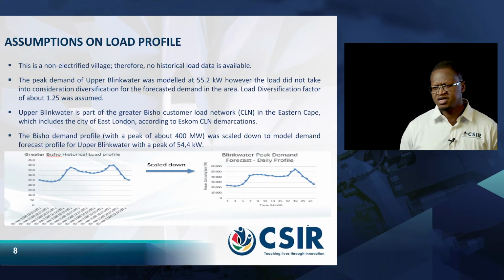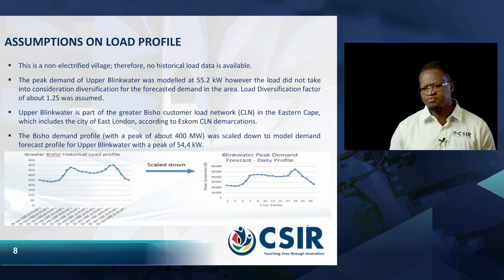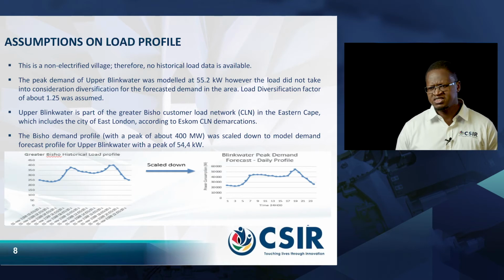In terms of assumptions, the main key assumption was on the load profile. As the village has not been electrified before and is not yet connected to the local municipality in terms of electricity, there was historical data unavailability, so we could not directly get a picture of the load profile. We went to ESKOM and requested the load profile for the larger municipality, the Bisho customer load network, under which the Raymond Mhlaba Local Municipality falls, and scaled it down to the Upper Blinkwater peak to come up with the load profile of the area.